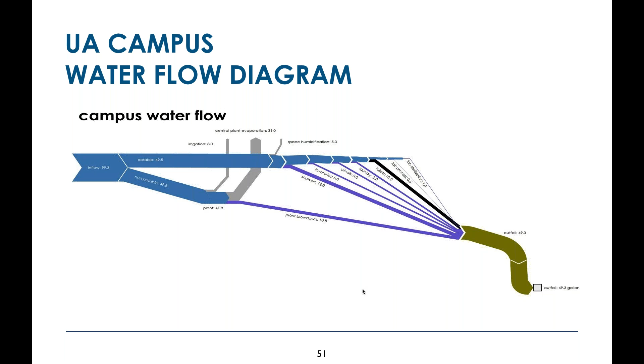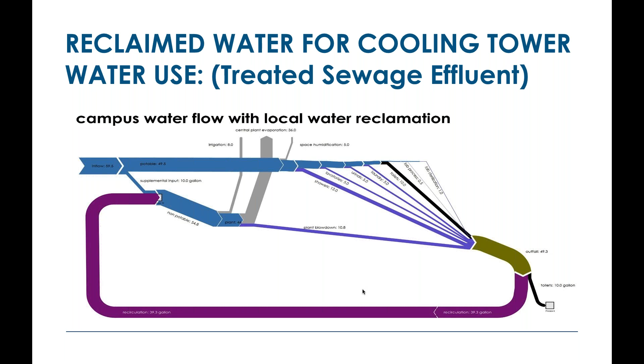The opportunity is to recover that water, treat that water at the county sewer system, and pump it back onto campus. That's significant since we use about half of our water for cooling towers. If we could use reclaimed water, that would cut campus domestic water in about half.